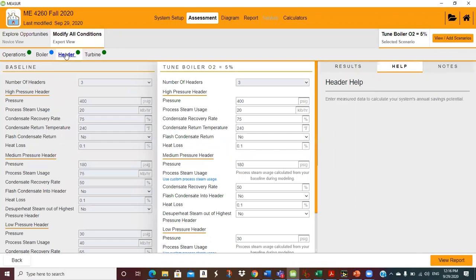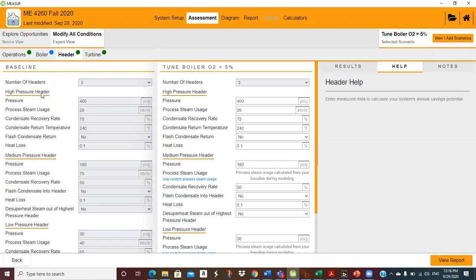Looking at pressures: 400, 20,000 pounds an hour, 75% condensate return, condensate return temperature. I have told Oak Ridge about this — they list the condensate return temperature under the high-pressure header, but this really goes back to the de-aerator. Why they list it under the high-pressure header, I have no idea. It doesn't make any sense. I've told them that a couple of times and they've never chosen to move it, but they need to, because it's just misleading.